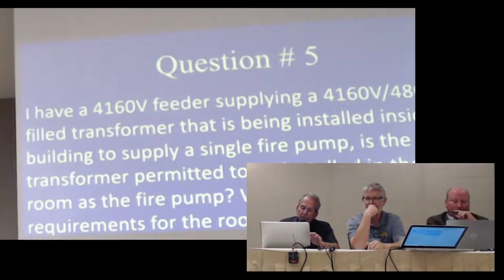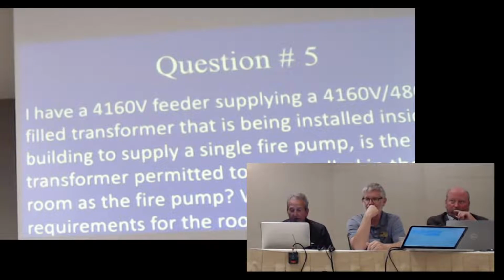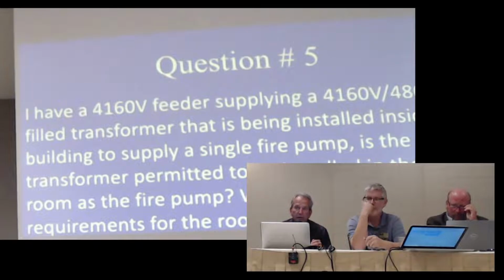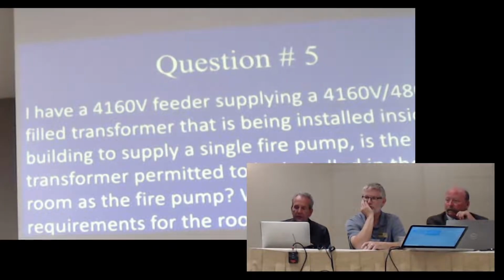Okay, first of all, 450.26, which is the controlling article about oil insulated transformers installed indoors, says they shall be installed in a vault constructed as specified in Part 3 of this article. Part 3 of Article 450 describes in detail what's required of a vault, including 3-hour rating, 4 inches of concrete, specific rules on sills, doors, vents, etc. Now, this is specific to oil filled. There are other fluids that are used in transformers where these rules would not necessarily apply. And there are 2 big exceptions.